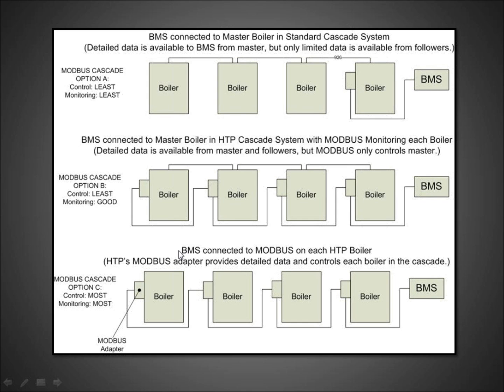This just gives you a little bit better idea of three ways in a multiple circuit installation where you have cascaded boilers. There's four represented here. You can see the building management systems. But the first one illustrates in option A, it says ModBus Cascade, control least and monitoring least. And what we mean by that is the building management system connected to the master boiler in a standard cascade system. Detailed data is available on the building management system from the master, as you can see here. You've got that direct connection from the master, but only limited data available from the followers.